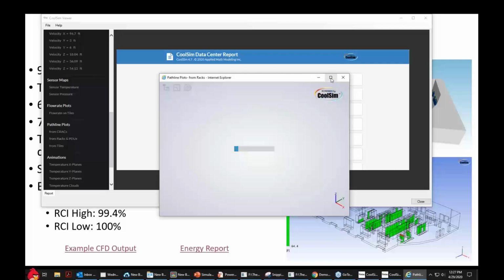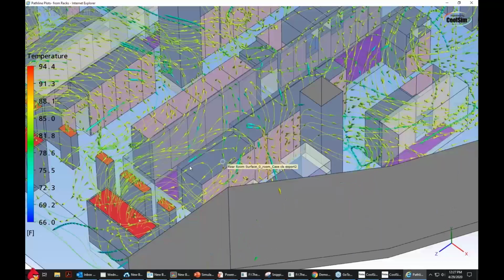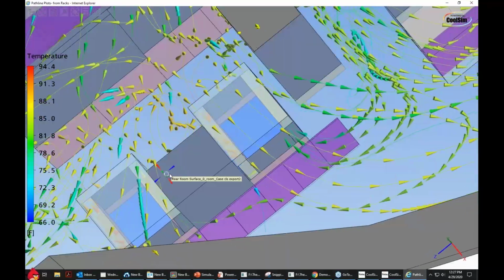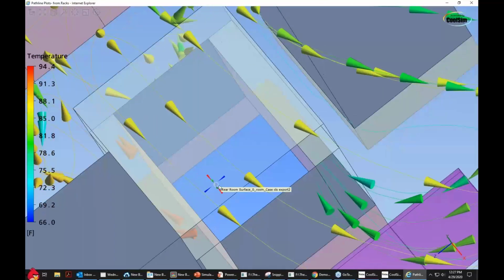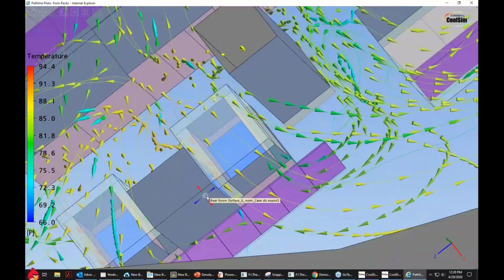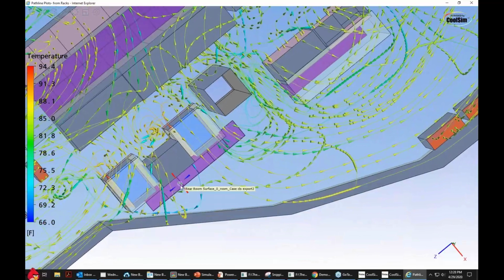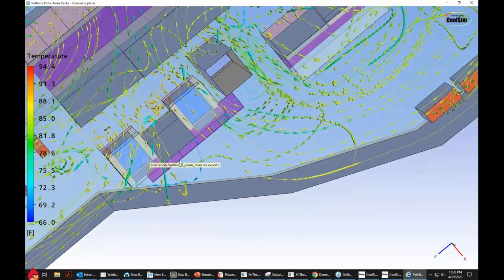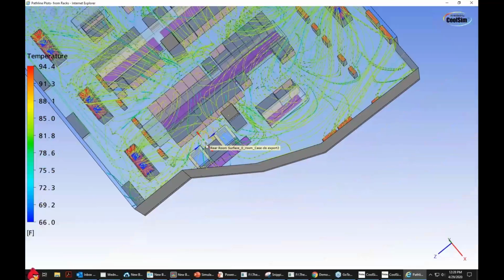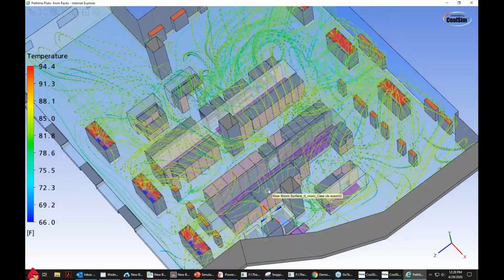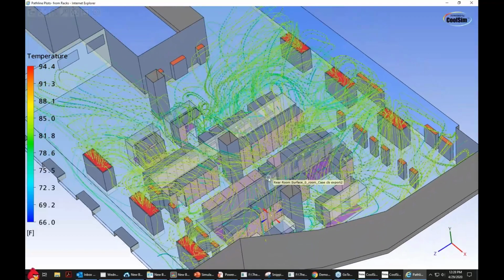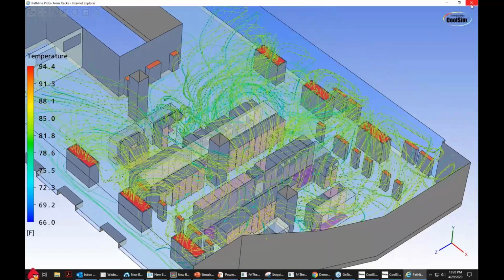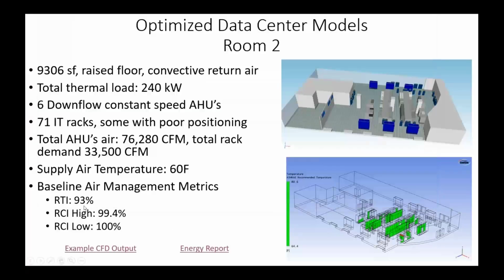So let's take a look at the path lines from racks. I think you can see it there. These are path lines of air coming out of equipment, and you can see over in this range we've got some side breathers here. These are side to side, very hard to manage from a containment point of view because they don't breathe normally. You see air coming out of the back of these devices and from side to side. Communication equipment is often like this. So I was not able to contain this section, and that's where you're seeing some of the hot spots. But again, as long as you know that, the issue of containment is one of knowing where your hotspots are going to be and managing them. That's how you handle that one. RTI 93, RCI high 90, 99, and you can see over here that problem occurring on those side to sides.